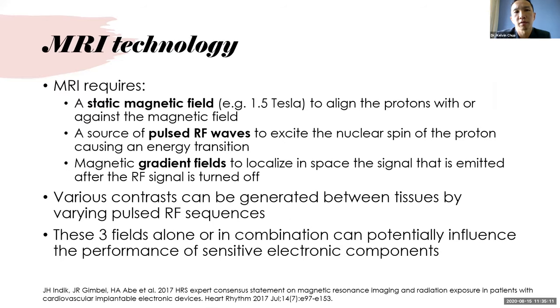So what makes MRI special with regard to our devices? First, an MRI has three main fields used for scanning. There's a static magnetic field—this is what's referenced when discussing a 3 Tesla or 1.5 Tesla MRI machine, which indicates its strength. This field aligns the protons with or against the magnetic field. Through this static magnetic field, a radio frequency pulse is released to excite the nuclear spin of the proton, causing an energy transition that is then detected by the scanner.